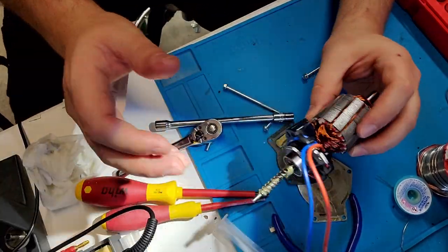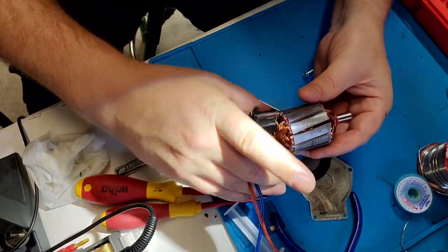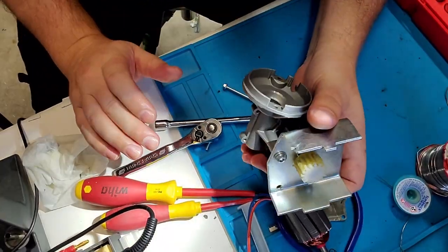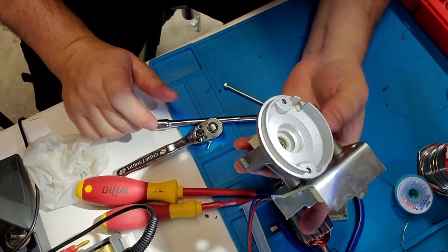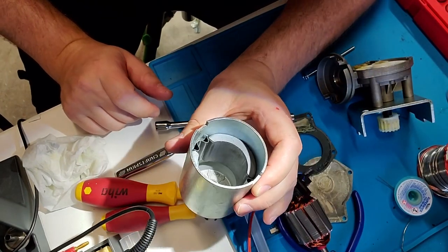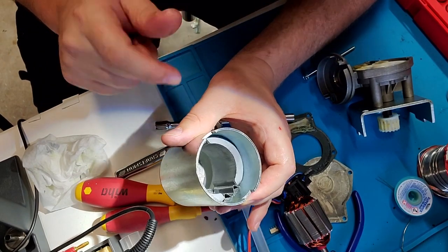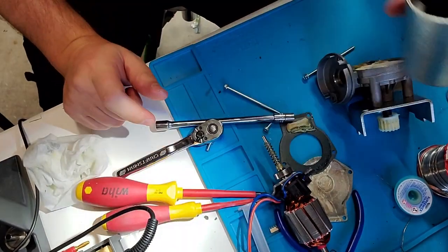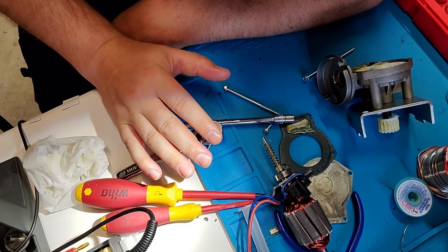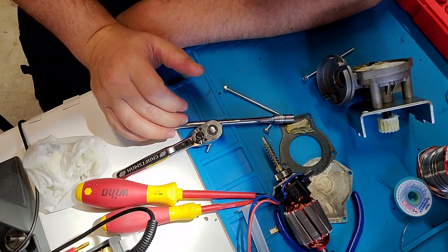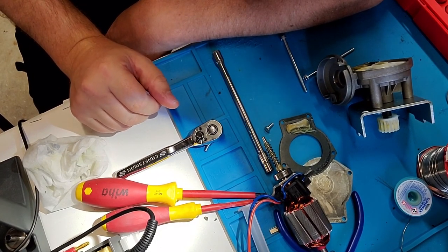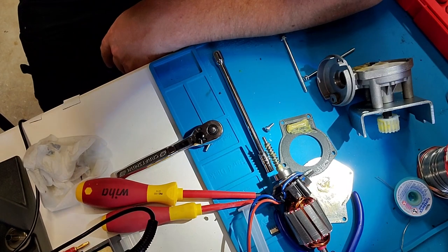This one does not have that, but it's a low use product, so it's probably going to outlive whatever vibrations it gets, especially since they balanced it so well. But yeah, normally these guys here would have some sort of epoxy. If I were to pull apart one of the motors for a power tool, guaranteed that they're going to be epoxy. That's just because it's probably a higher use tool, but it is what it is. So guys, this motor was actually fine. Everything about it was fine. The transmission was fine. It runs. It runs beautifully. The grease is still fresh. I have no idea why this patient lift, the motor was changed out. No idea at all.